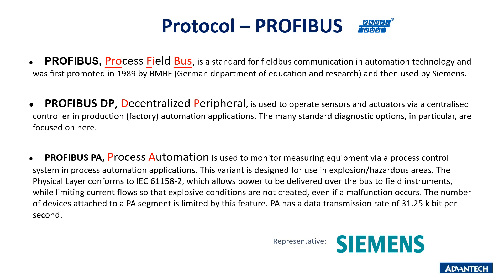Profibus PA, process automation, is used to monitor measuring equipment via a process control system in process automation applications. This variant is designed for use in explosion or hazardous areas. The physical layer conforms to IEC 61158-2, which allows power to be delivered over the bus to field instruments while limiting current flows so that explosive conditions are not created, even if a malfunction occurs. The number of devices attached to a PA segment is limited by this feature. PA has a data transmission rate of 31.25 kbit per second.